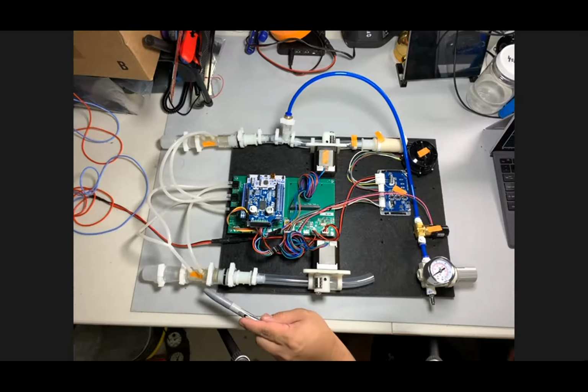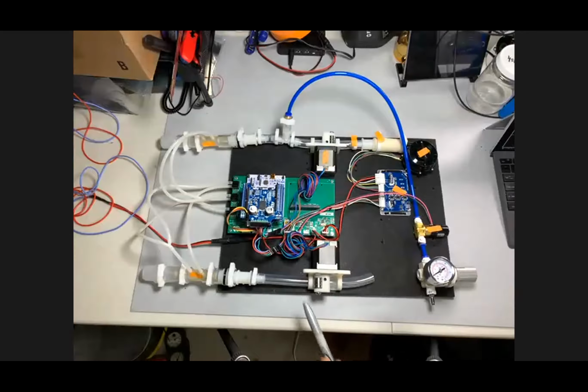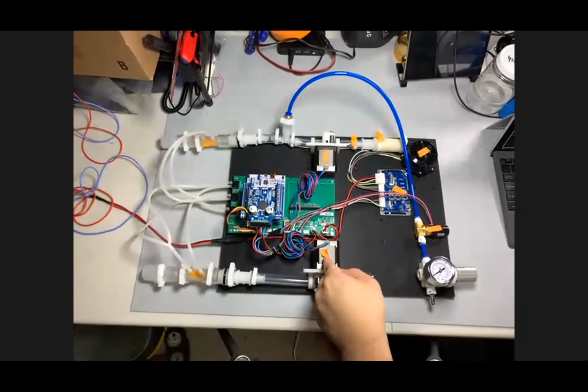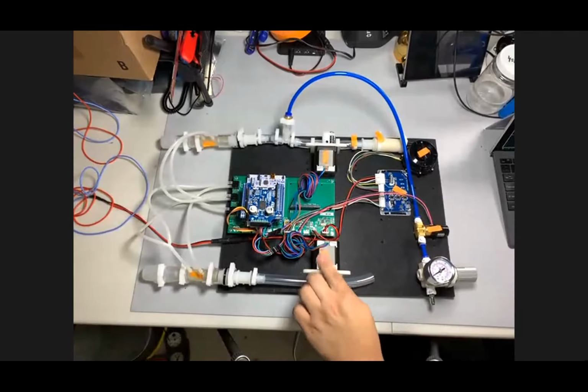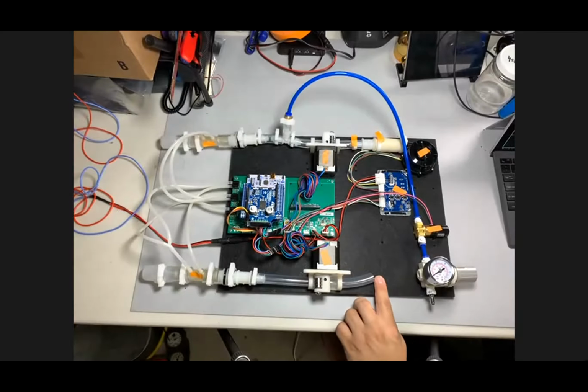Moving on downstream from the exhale, Venturi flow sensing, we take that step down. We come in through here to the pinch valve, which we just talked about. So that one as well is fixed. And exactly as Elizabeth mentioned, there will then be a filter on the outlet side to prevent contamination. That is the end of the pneumatic loop.